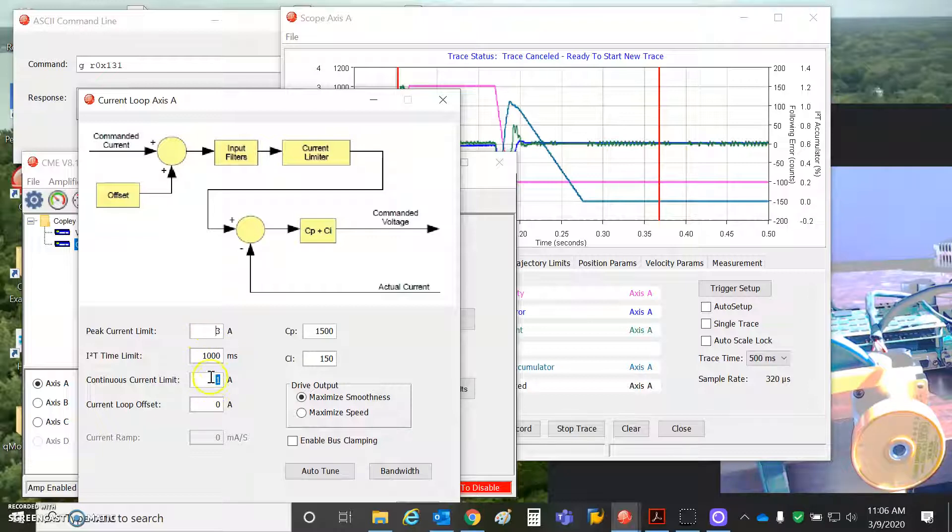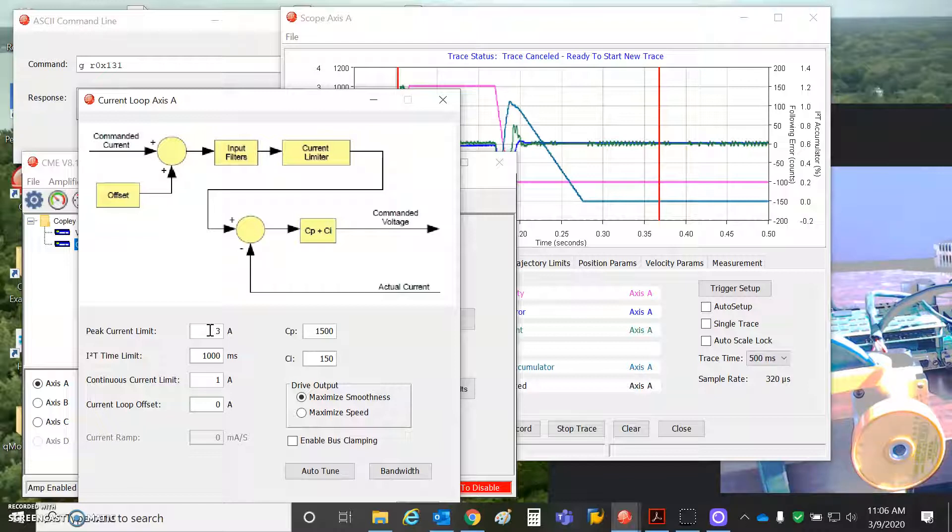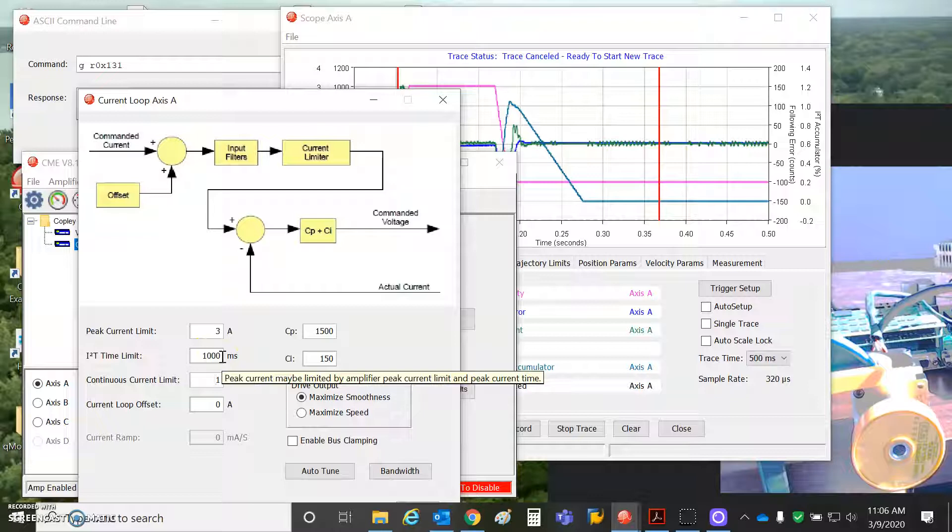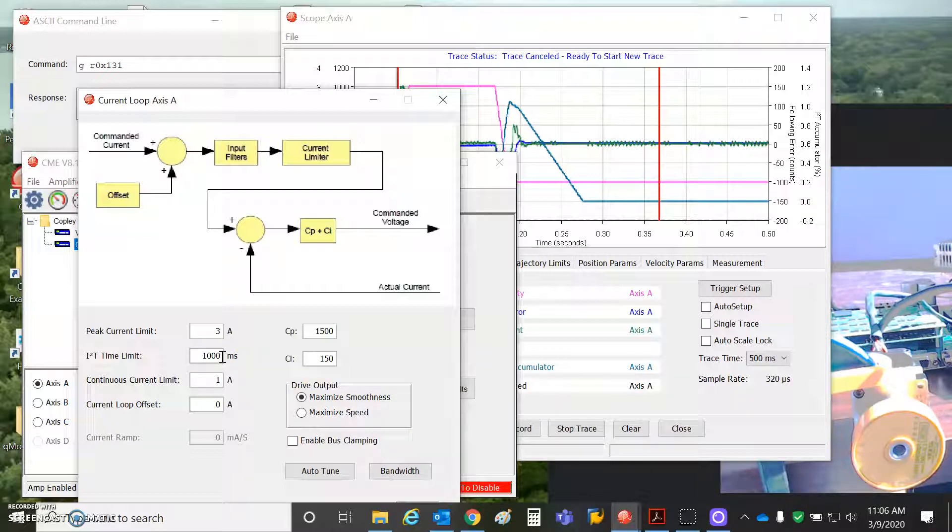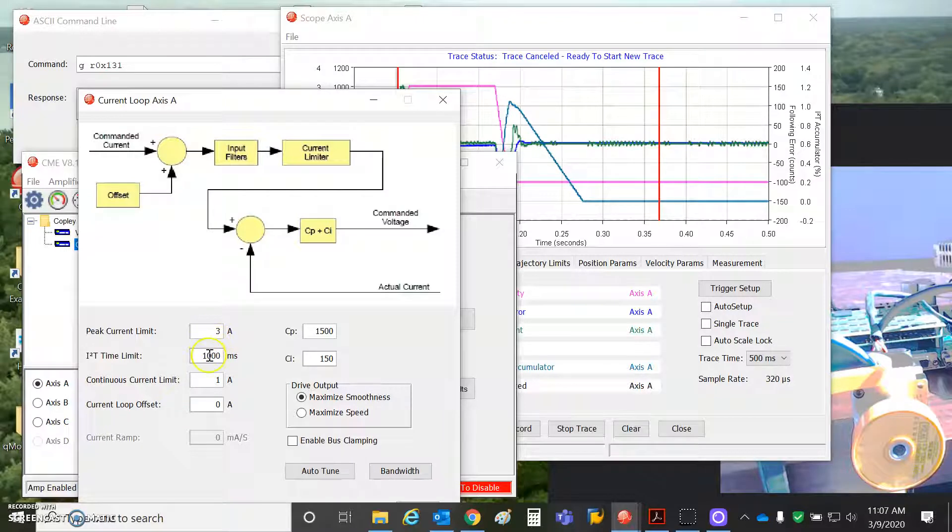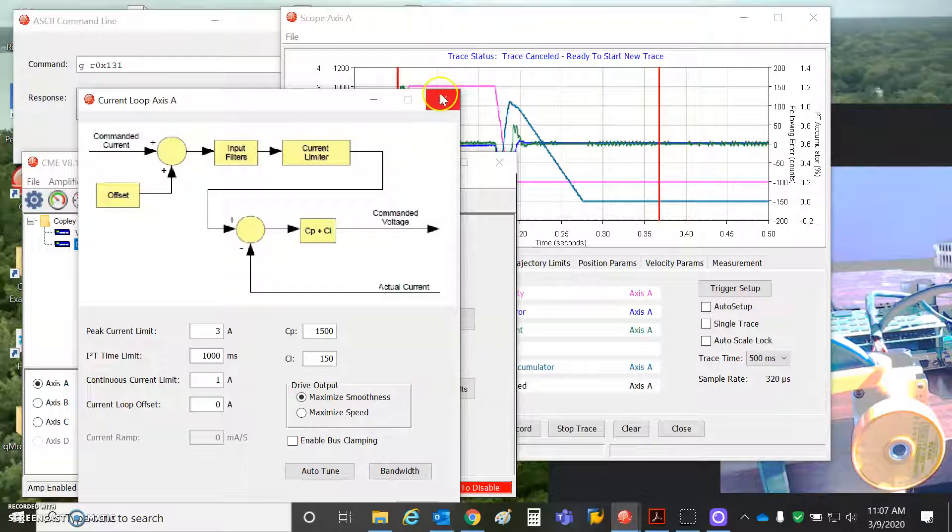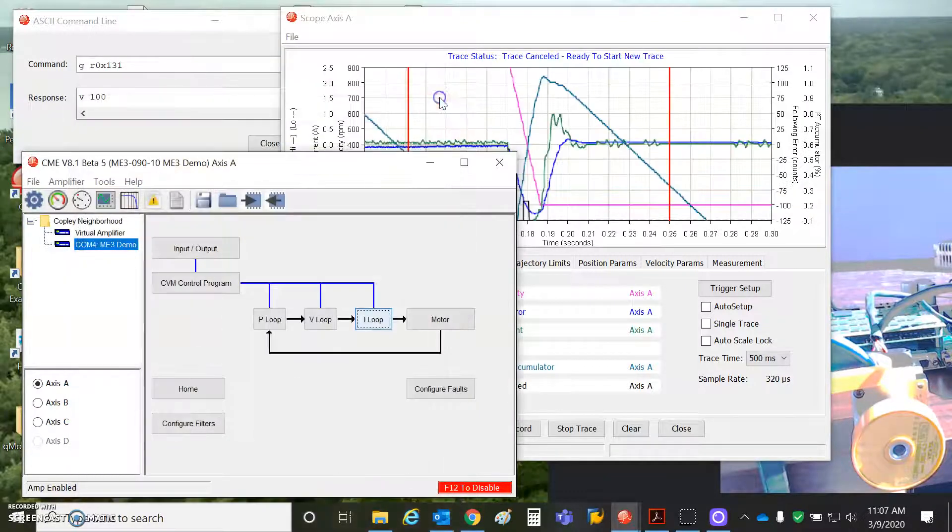And then a typical peak current would be 3 times the continuous. The bigger the motor, maybe the more. The Maxon motors have a ridiculous number, but then you've got to cut the time down. So maybe you could do 10 times the rated current, but for like 100 milliseconds. And with a very large motor, maybe you could do 2 or 3 times that for 5 seconds. It all has to do with the heating effect of the coil.